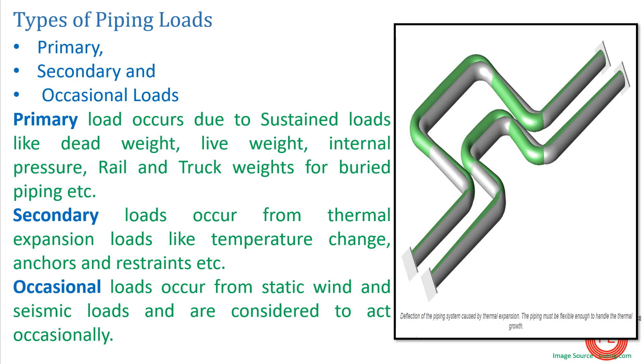Different types of piping loads are generally divided into three categories: primary loads, secondary loads, and occasional loads. Primary loads are the self-loads of the system. These include the dead weight of the pipe, the live weight due to fluid moving through the pipe, internal pressure — since pressure equals force upon area — and rail and truck weights for buried piping.